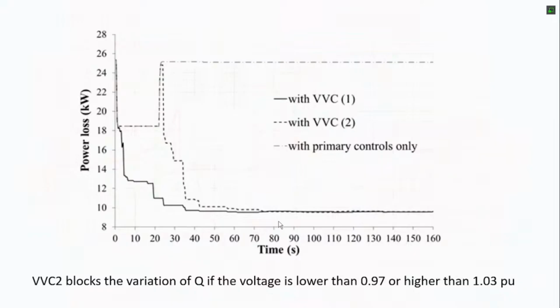So you see that the behavior is practically the same. VVC2 is less active because at the beginning there are several voltages that are outside this limit. So at the beginning the primary control acts, and also the transformer. So you see here the change that is due to the tap of the transformer changing, and then this secondary voltage control acts afterwards.